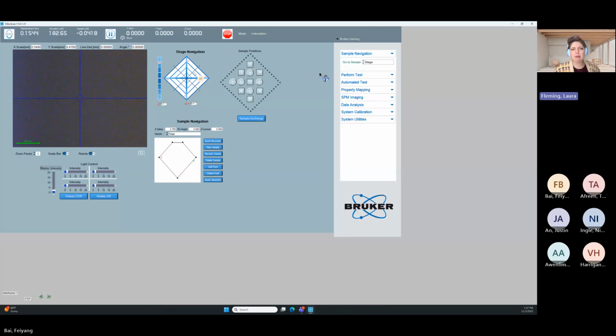Once you get down to more fine movements, we highly recommend doing slower, longer moves rather than really quick, short moves. The reason is that your stages are not encoded. So if you do a bunch of short, quick moves, you might run the risk of the steps being off. The system doesn't like it. The software might crash. So longer, slower moves rather than many short, fast moves. You also have your Z, which works the same way. So this brings the Z stage up. This brings the Z stage down. And the speed is dependent on where you click here.